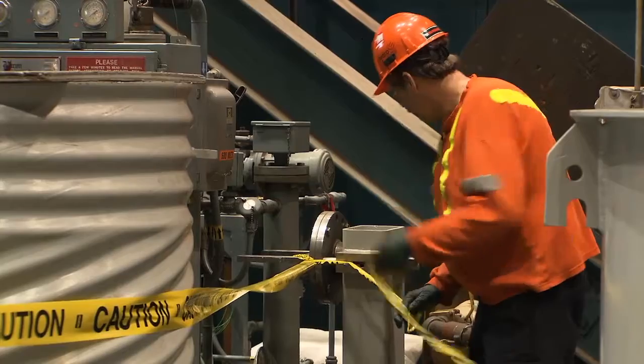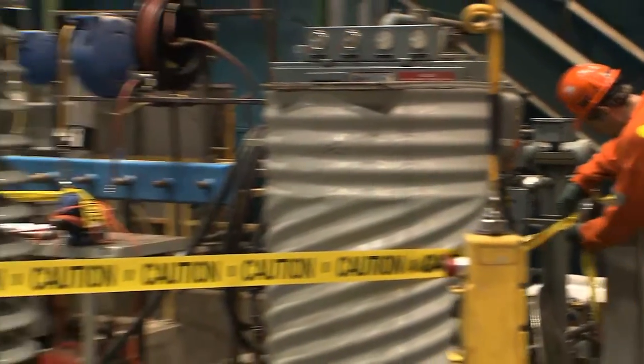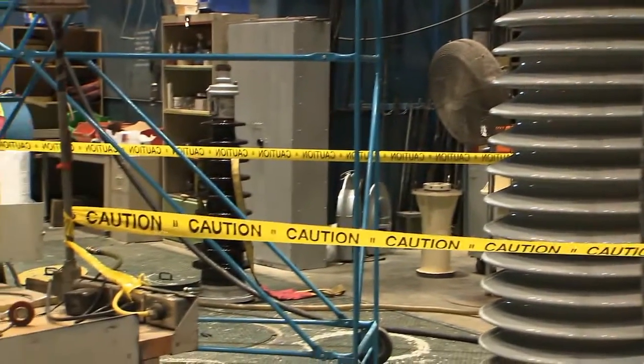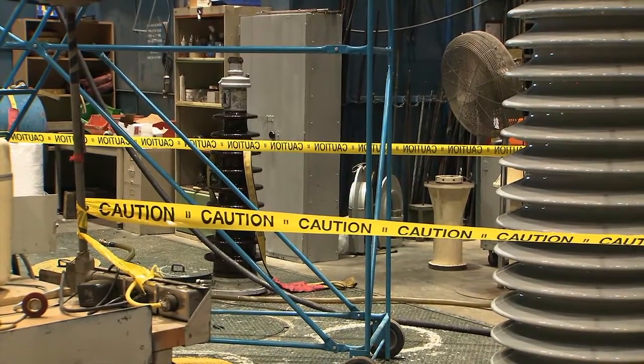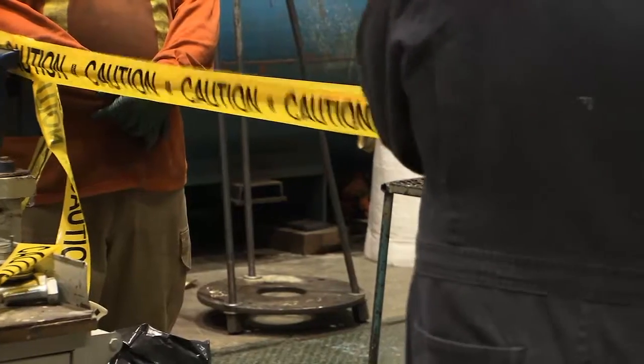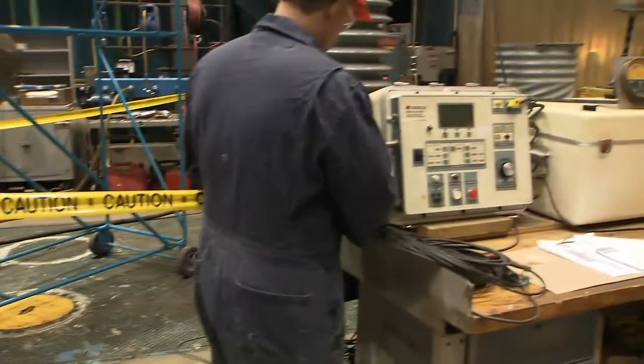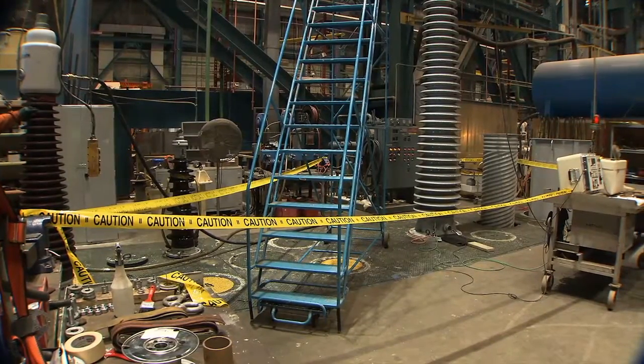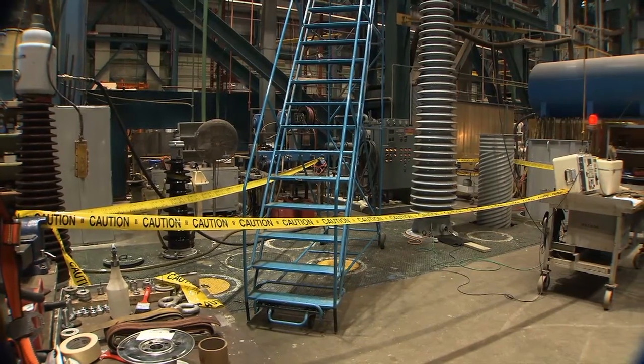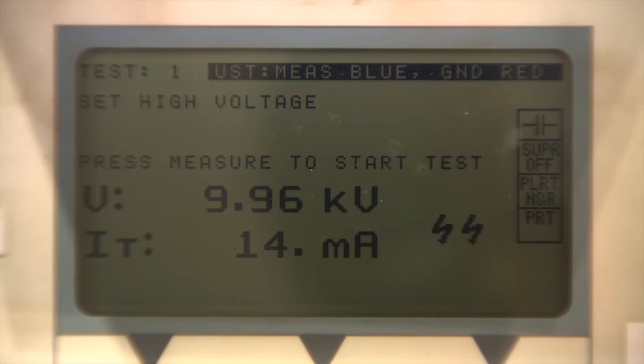Rope off or use tape to seal the area and prevent anyone from entering it while the test is being conducted. Perform the C1 UST test using the Biddle test set and using the same procedure that was used for the initial electrical testing before the bushing was refurbished. This test is executed using a voltage of 10,000 volts.